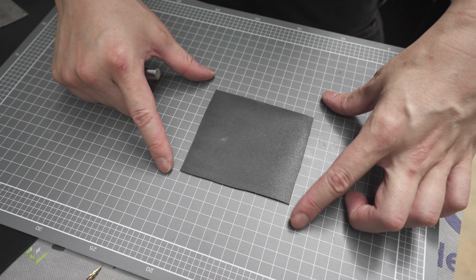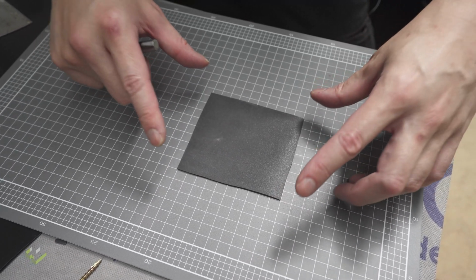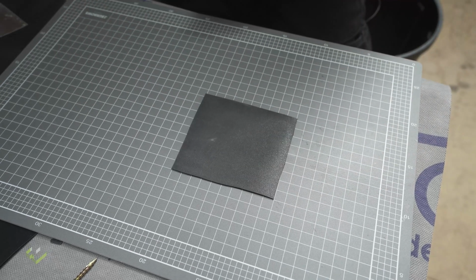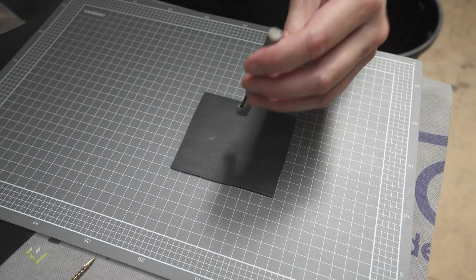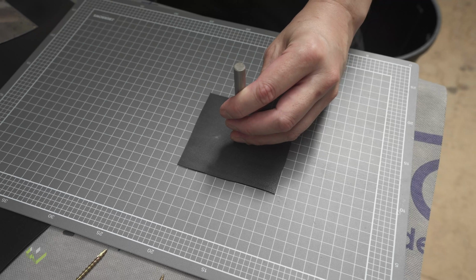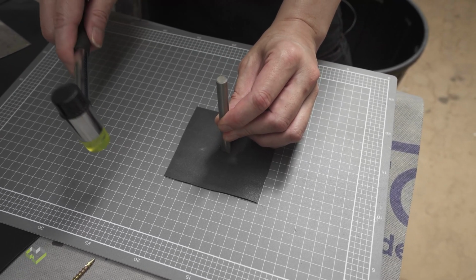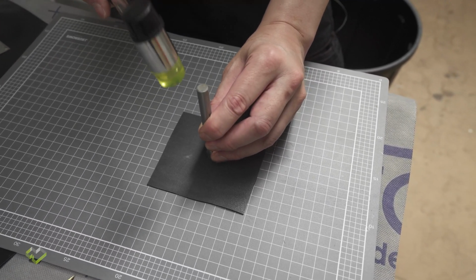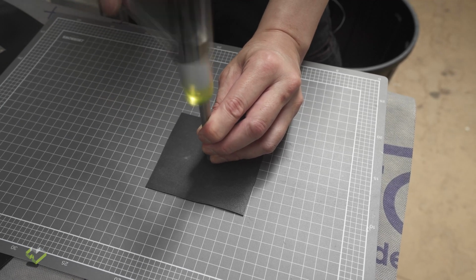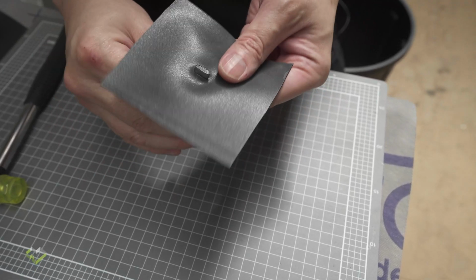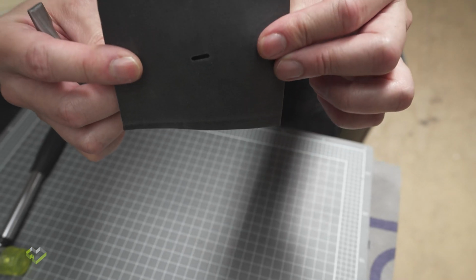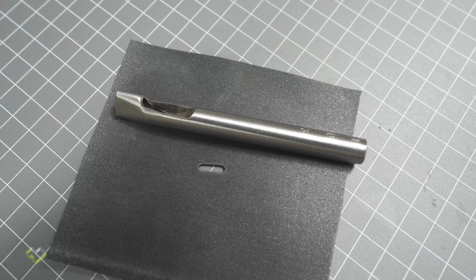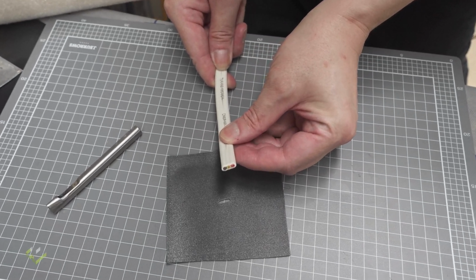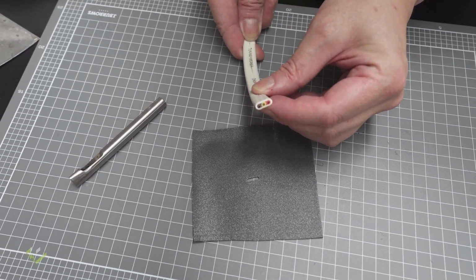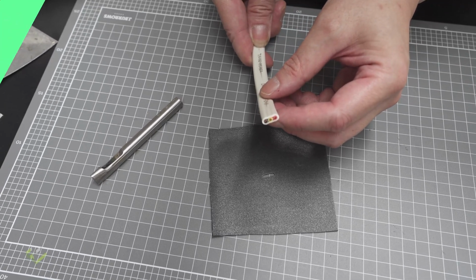When you order the rubber gaskets, we have different sizes of the square available. Pick the size that suits your need, and then it's very easy. You use a hole puncher that fits the cable that you need to penetrate. Preferably doing it on a proper cutting mat, that would make the cut a lot cleaner. And then you just use a hammer. Then it's coming off and you got a nice and clean finish. When picking the right size of the hole puncher, you always try to make it at least 2 mm smaller than the actual cable or conduit that you want to put through the hole.